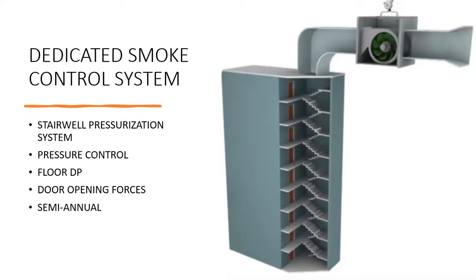That's interesting. We don't have that initial one for the latch in our code. The latch itself. Yeah, interesting. And so you could have a door hardware contractor involved as well, making adjustments for anything that's not due to air pressure, differential pressure, that's causing a problem there.